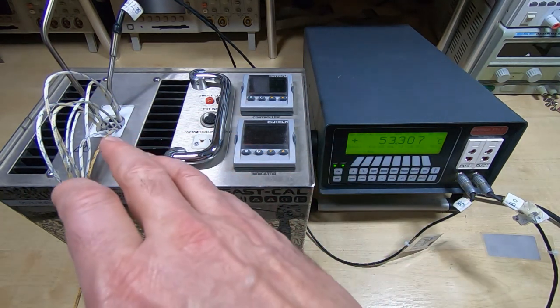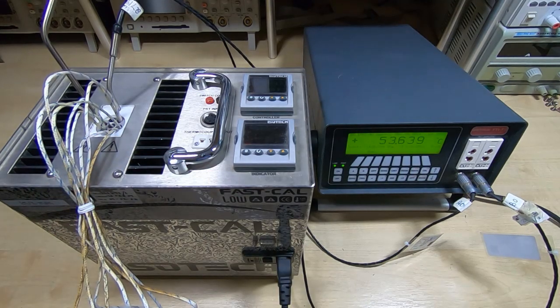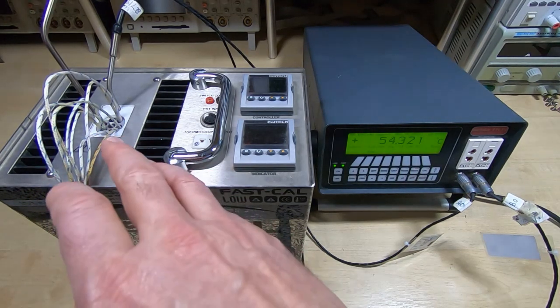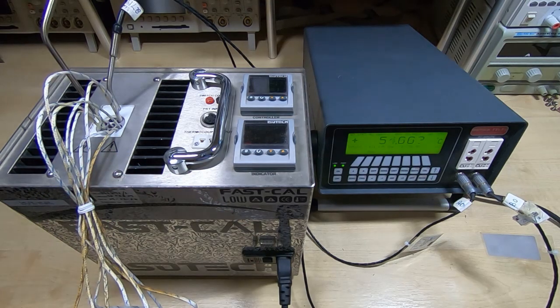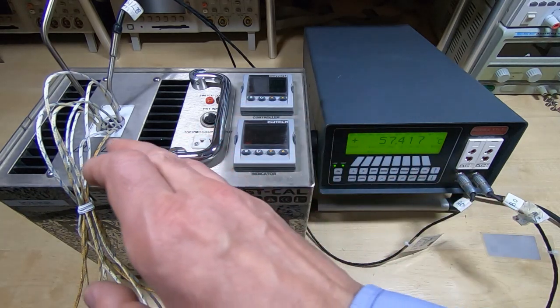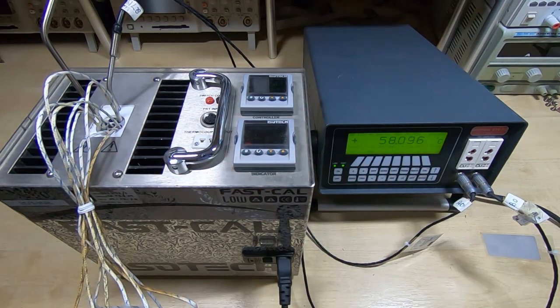The other thing, if you're going to do this and it's a high temperature application, it's well worth conditioning the thermocouples first. If you turn them up to high temperatures, they will tend to change their characteristics slightly for the first few runs. So what I did with these, I left them at 250 degrees for 3 hours before I started the calibration process, and that just makes sure that the bulk of the change is going to occur before I start trying to use them.